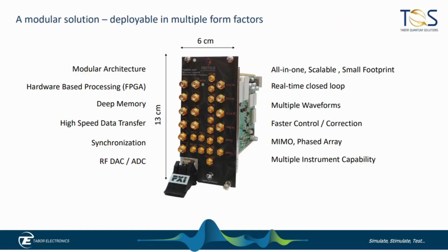You may have noticed on the last slide that the instrument architecture is modular. We put each module in the different form factors, i.e. the PXI, the desktop, or the benchtop. It allows you to scale your instrument in whichever way you want. If you want many hundreds of channels with high speed, you would use the PXI version. If you want a nice, easy-to-use benchtop, you can configure it from 4 to 8 channels. And the same with the desktop, but just without the screen.